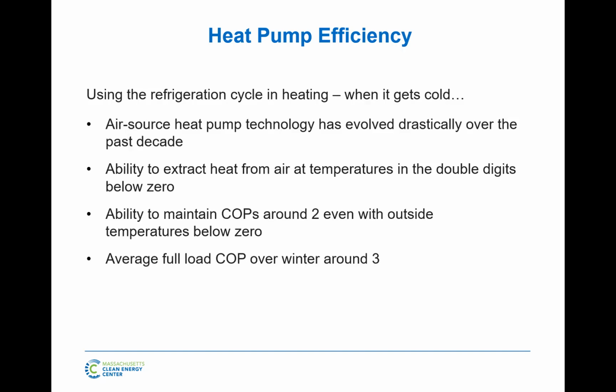This is everything I just said, I think, in a slide. Just so you know, on the coldest design days, whether you use 7 degrees, 0, even if you use -4, around that range, people ask me, okay, what's your COP at 0? Doesn't the COP get down to 1? Well, it doesn't. So even at 0 or -4, the COPs of commercial air source heat pumps are going to sit around 2.